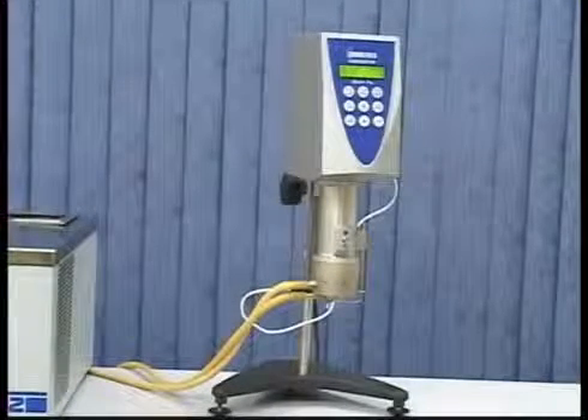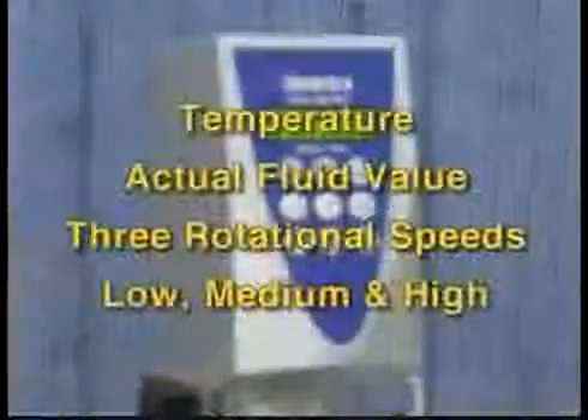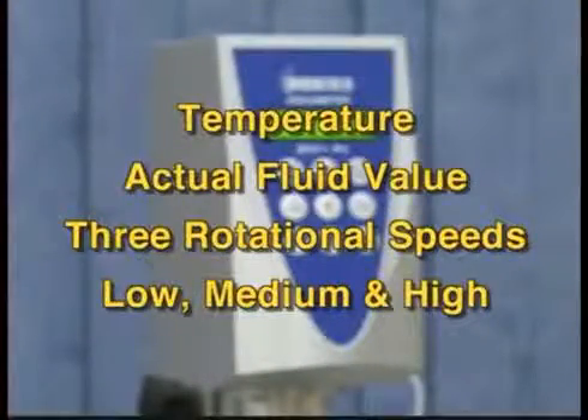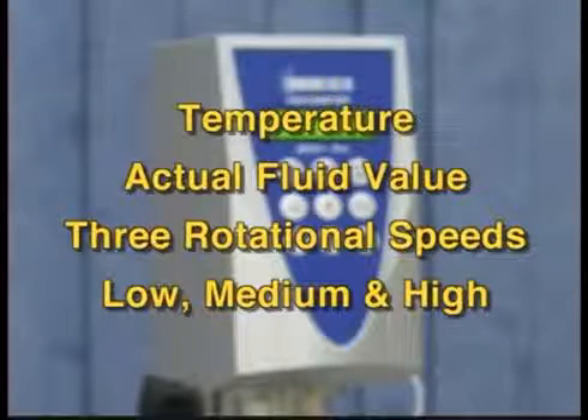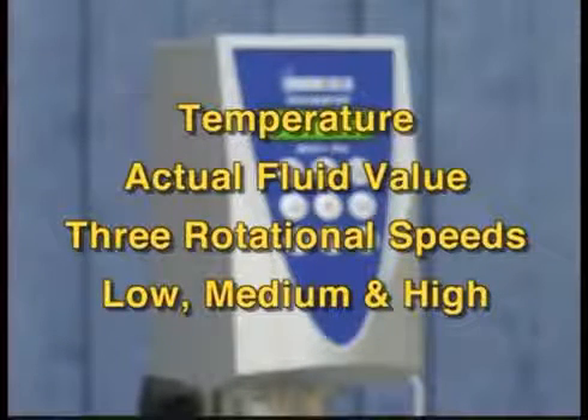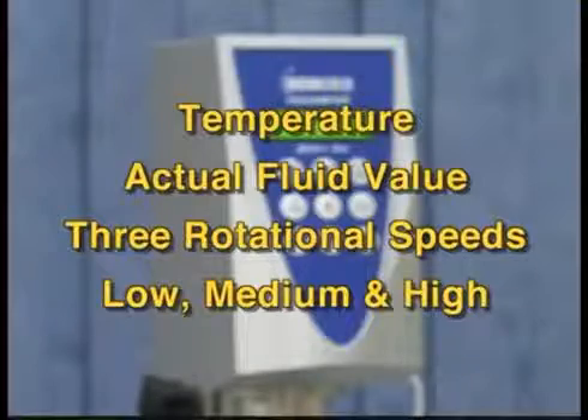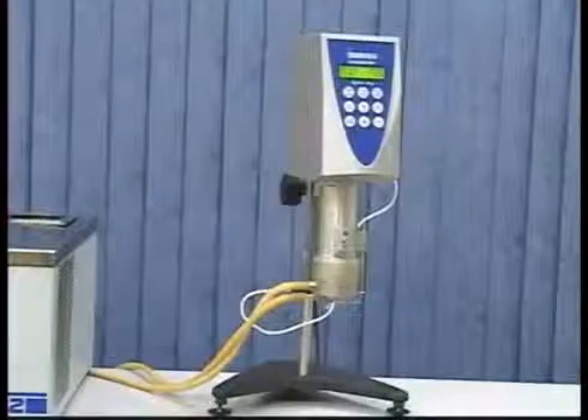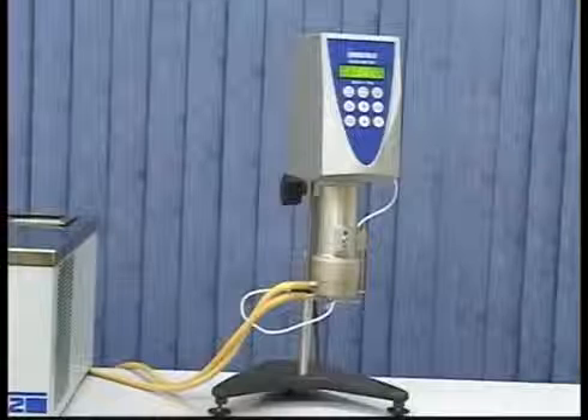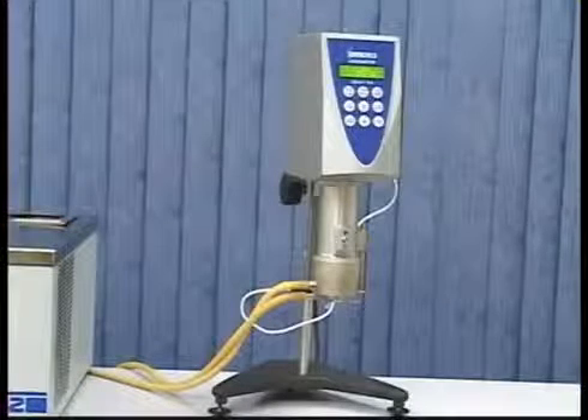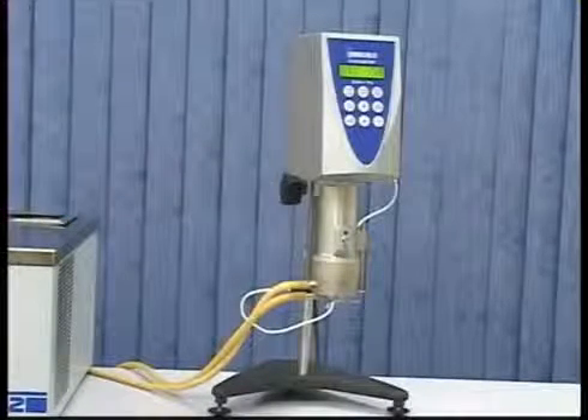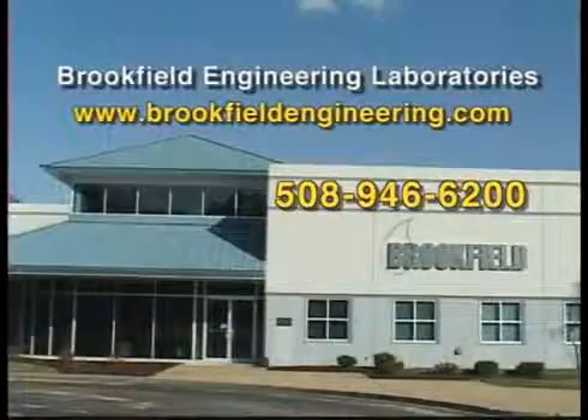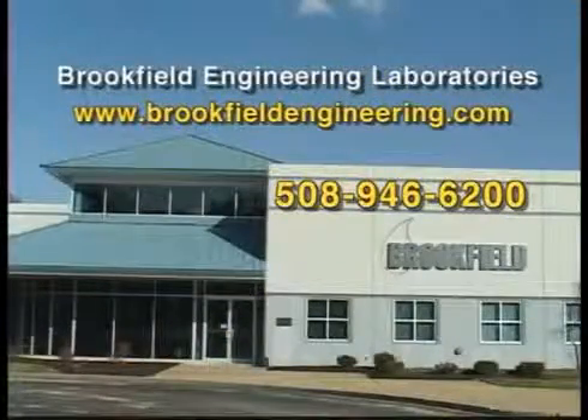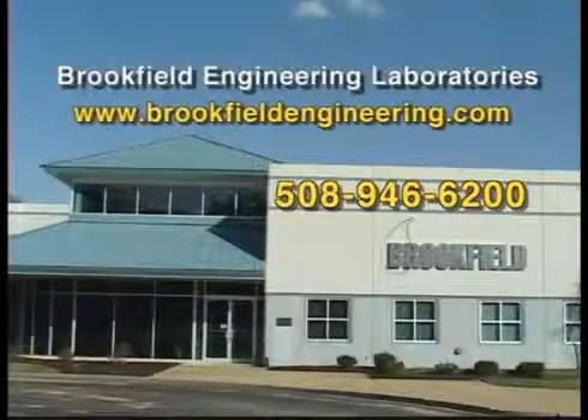Remember the important aspects of performing a calibration check. Good temperature control. Use the actual fluid value for the viscosity standard at 25 degrees Celsius. Select 3 rotational speeds based on the associated viscosity ranges that provide low, medium, and high torque readings. If you find the instrument is not within tolerance after performing a calibration check, repeat the test to ensure that everything was done correctly. If your instrument is still not within tolerance, contact Brookfield Engineering or an authorized dealer.